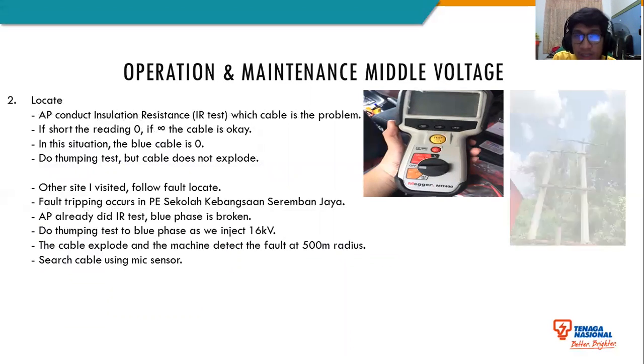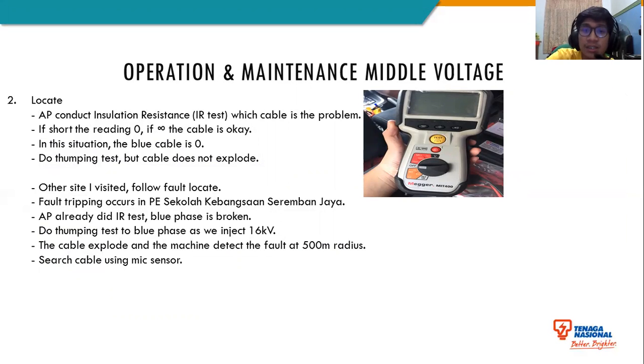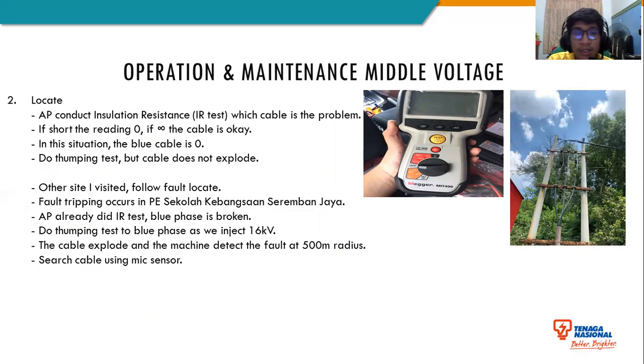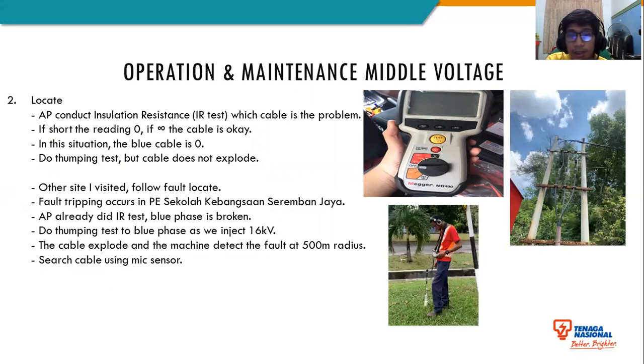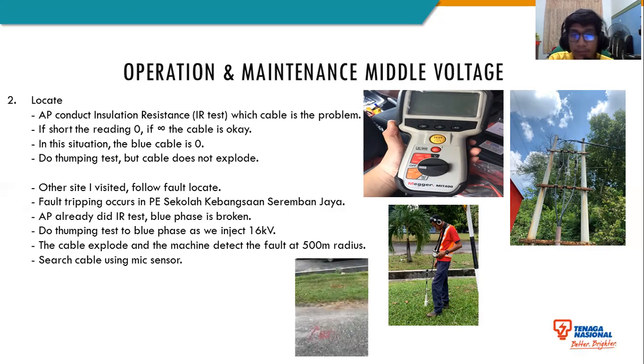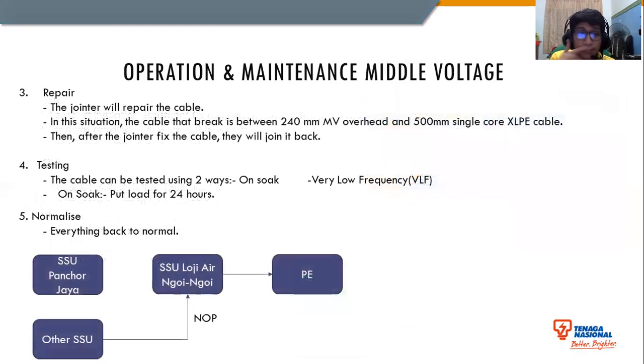So the cable uses a mic sensor. This is the Megger, the device that we use for the IR test. This is the cable that broke at the first site, and this is the mic sensor that we use. We search for the fault, and we mark it down so that the jointer can repair the cable.